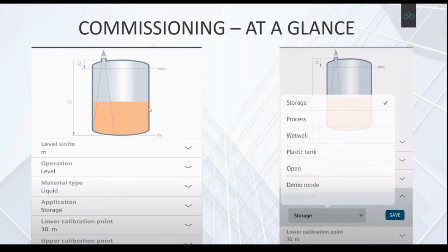So it's a very intuitive graphical user interface. You choose your level, for example, material type. So you can have this example for obviously a liquid. You've got your minimum, your high alarm or your high level, and you've got your low level, if that's the bottom of the tank or whatever. You can set as you like. So these are the lower calibration points and the upper calibration points.